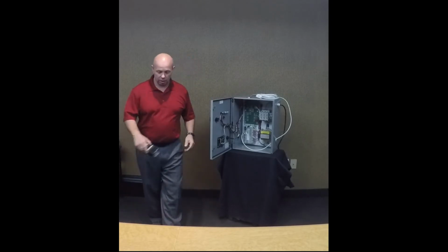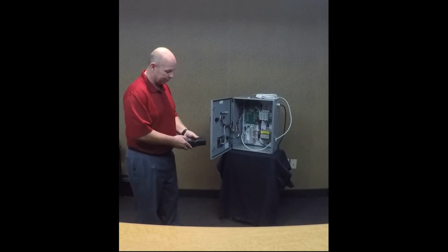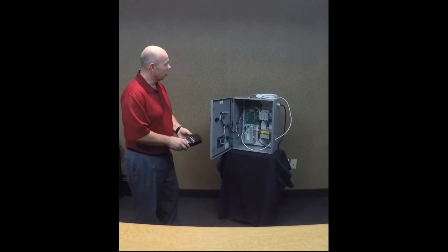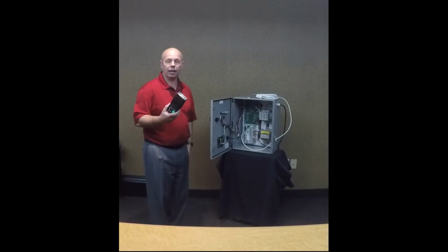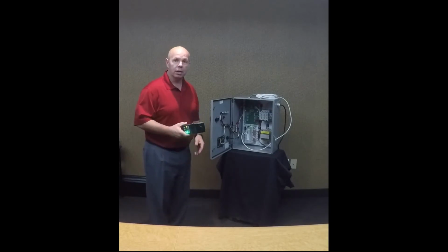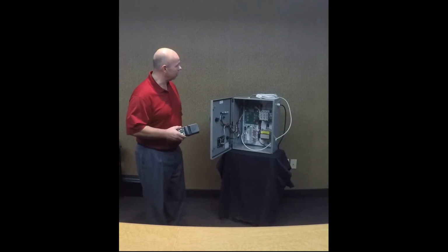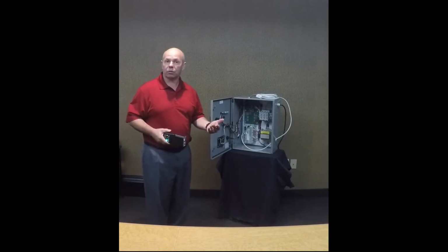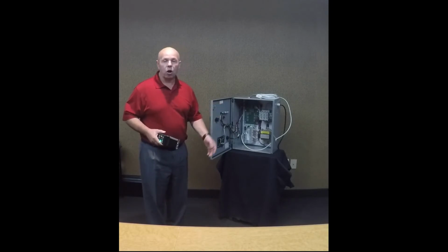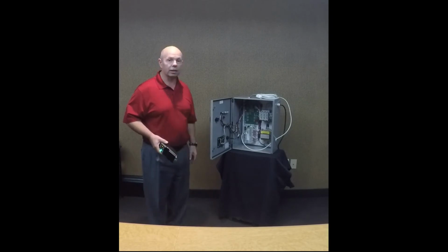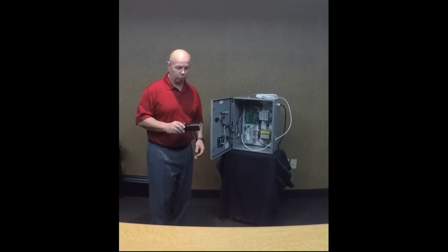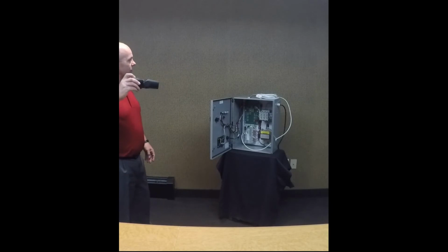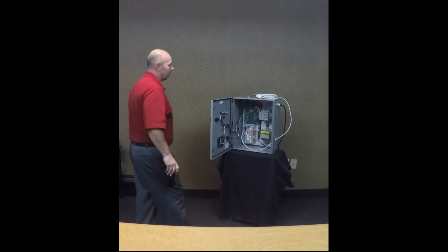So now we have this system fully operational. We're going to test this out by using a 4 battery camera flash. A regular camera flash from like your Samsung phone or your Apple iPhone will not have enough intensity to actually trip the sensor. You need something with some pretty good light intensity. So we'll get back here so we get a nice good flash from a distance. And you can see how it senses that very, very quickly.